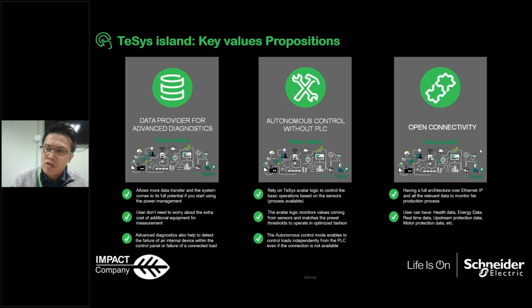And then the last but not least is open connectivity, because with the TeSys island, if you remember, we are communicating with the system using Profinet, Modbus, Ethernet, Profibus, which are all open connectivity. So this is not a proprietary system of Schneider. Even though your existing system is using Siemens or ABB or Rockwell, it doesn't matter, because we do not use a proprietary protocol or proprietary system, so we can communicate with other external parties.